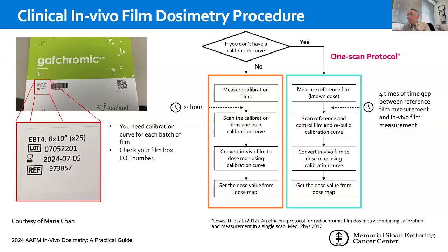And then we'll measure a reference film, as we have mentioned earlier on. And then we'll wait for a time defined by the time difference between the reference film and the clinical fields. For example, if I measure our in vivo dosimetry at 12 o'clock, and then we measure a reference field at 1 o'clock in the afternoon, so we have a 1 hour separation. We don't want to scan the film until at least 4 hours after our reference fields. And once we have that, we then scan that and follow the same procedure to generate the dose map on the clinical field. The reason, as I mentioned earlier on, to do the reference field is really to rescale the calibration curve to the day of our clinical fields, to reduce any uncertainty due to scanning or other issues in terms of output or scanning.